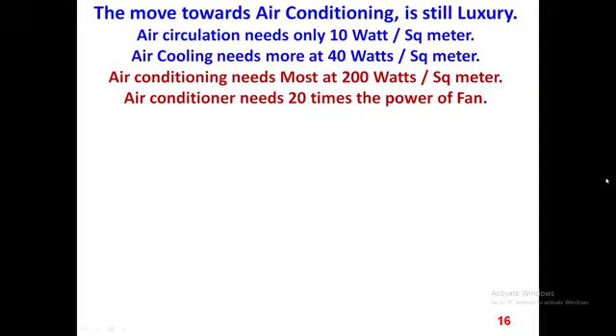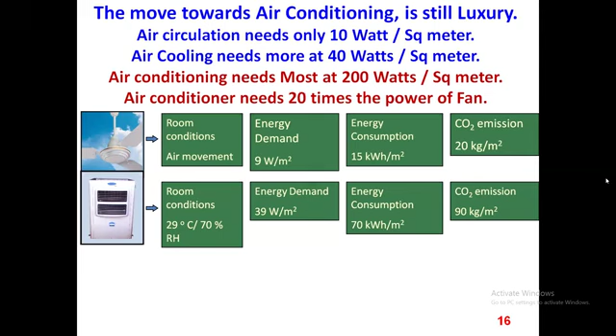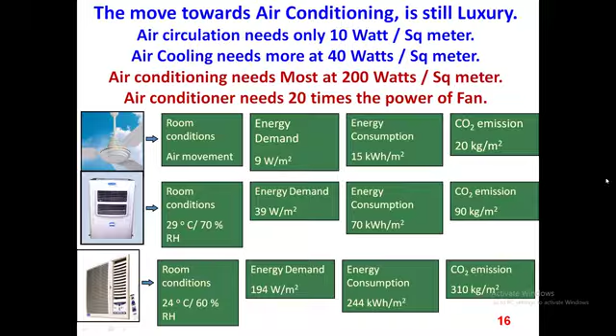The first point which I was referring to: air circulation consumes only 10 watts per square meter, whereas air cooling needs around 40 watts, whereas air conditioning takes around 200 watts per square meter. This is where air circulation is getting superimposed on an air conditioner, especially thanks to BLDC or brushless DC fans, where the mild circulation of air inside a room or hall maintains the heat load, and the air is well circulated so that the evaporation loss from the human body is also removed. Ultimately, circulation gains more importance than air conditioning now. The government has already made a mandate for 24 degrees, and many industries and buildings operate at 27 degrees within the air conditioned premises, and they see human comfort as excellent.